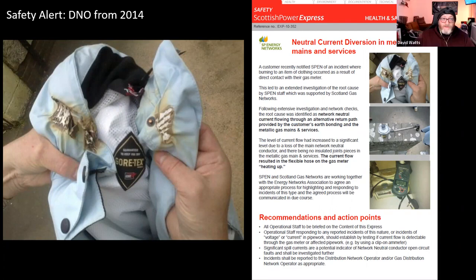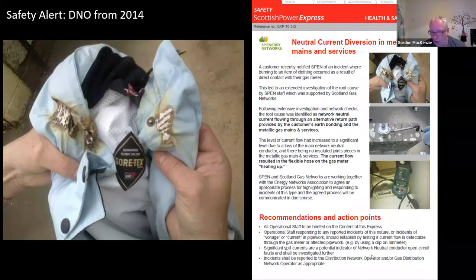Yeah, and fundamentally the test isn't hard. It's not live testing to the point of actually creating exposures. It is a simple test to do. The information that came from the field staff initially for that incident was that there was voltage. They were reporting voltage on the gas pipes. So there was no precedent for applying a clip-on ammeter at that particular time. And it's only when we got the information about the jacket that we said, well, it's no voltage, it's set fire to the jacket, it's obviously current. Go and clip that clip-on ammeter onto the pipes and tell us what you find. And I think in the property they were in, it was like 35 amps, something like that, flowing through that. So we knew at that point we had that.